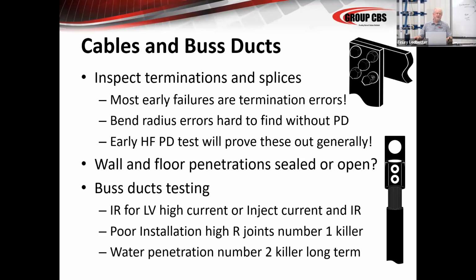Cables and bus ducts, you have to figure that in as part of your system. The cables run into armor cable, they run into bus ducts, they run up to a mile in the plant, 2 miles. In that, there are splices, there are manholes, there are terminations. There's all kinds of things in the cabling systems that need to be checked and tested. Most early failures are termination errors. So look at the quality of the terminations. A lot of that can be picked up with PD testing, with high frequency PD testing. But basically use your eyes, inspect the cables, inspect the terminations, inspect everything, trust nothing.